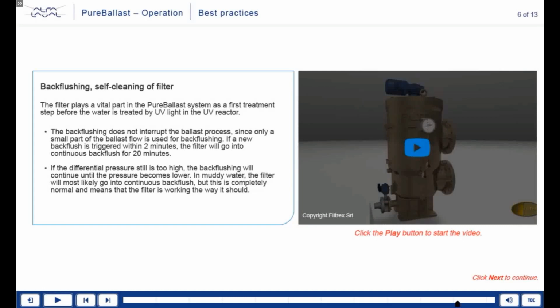The backflushing does not interrupt the ballast process, since only a small part of the ballast flow is used for backflushing. If a new backflush is triggered within 2 minutes, the filter will go into continuous backflush for 20 minutes. If the differential pressure still is too high, the backflushing will continue until the pressure becomes lower. In muddy water, the filter will most likely go into continuous backflush, but this is completely normal and means that the filter is working the way it should.